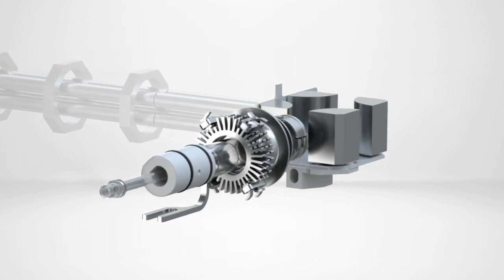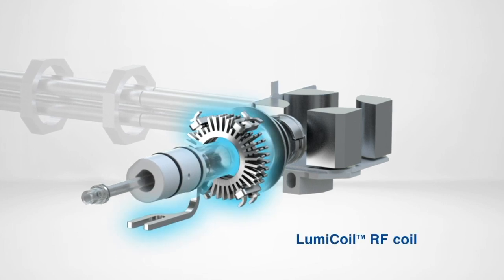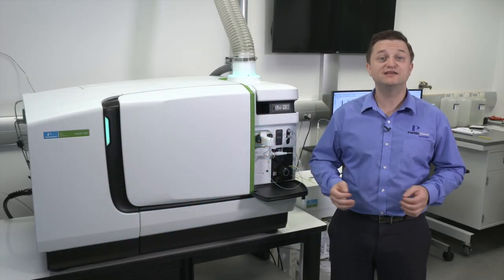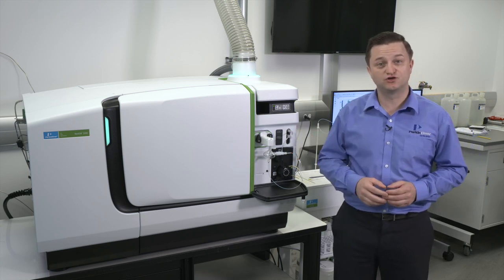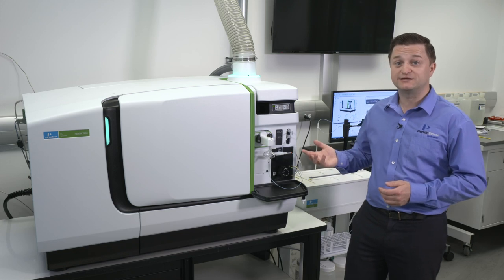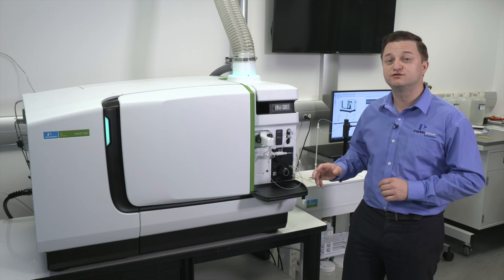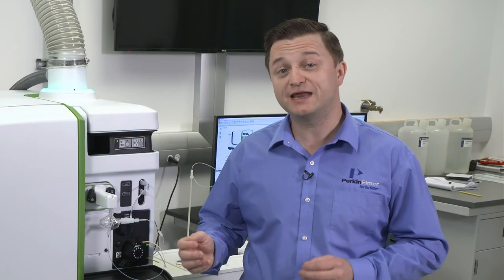The accurate and rapid impedance matching of this generator delivers unmatched stability and matrix tolerance through the patented LumiCoil technology. The instrument's matrix tolerance is further enhanced by PerkinElmer's all-matrix solution, or AMS for short. This built-in feature of the Nexion series allows you to use aerosol dilution to minimize matrix suppression and reduce deposition on cones when running samples with high total dissolved solids. Using AMS, bench-level dilutions are minimized and run time is maximized because of the lower cone deposition, maximizing productivity.